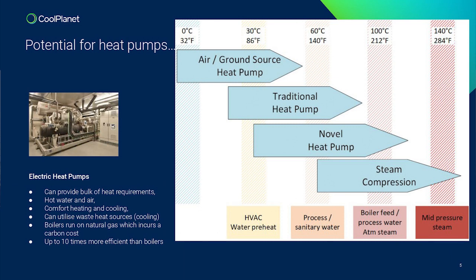That's a great point. Historically heat pumps have grown out of the refrigeration industry, so they've used traditional refrigerants like ammonia or the R gases, and they're really good at collecting heat all the way down to minus 40, minus 60 if you're in a blast freezer. But the sort of heat pump applications you typically see are collecting heat at 10 to 30 centigrade and warming it up to 60, maybe these days as high as 90 centigrade. That's a real sweet spot for traditional refrigerants like ammonia. It's really good if what you've got is heat that would otherwise go to a cooling tower, and you want to make heat for CIP, hand washing, or those sanitary wash-down processes - water at 60 to 90 centigrade is a real sweet spot for traditional heat pumps, and that works really well.